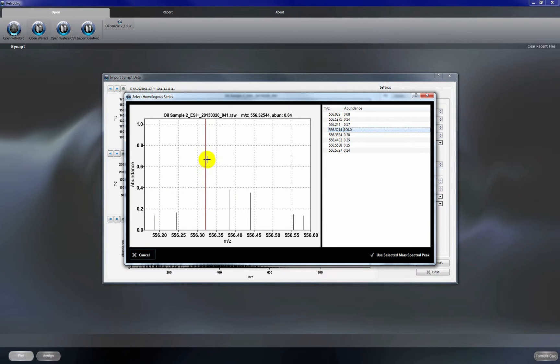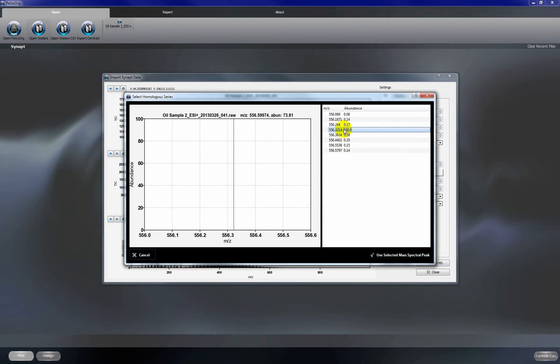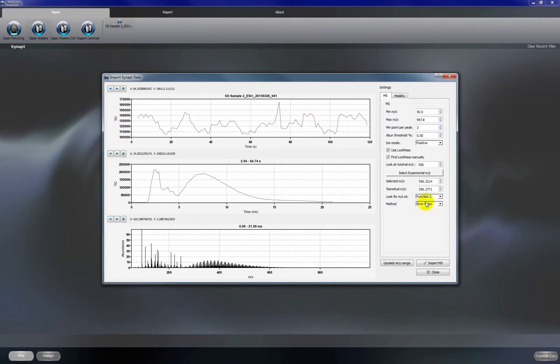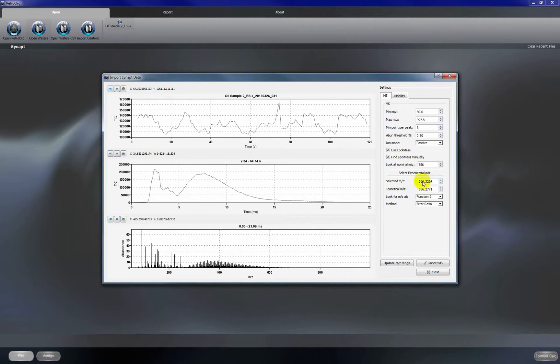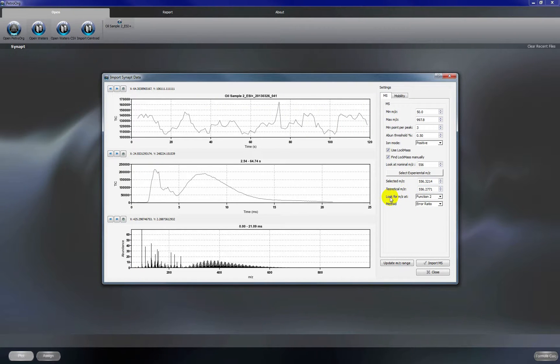When you click on these peaks they will highlight in red whichever one you've clicked and this is our actual lock mass peak. You can see here it's highlighted in red. When we zoom out by right clicking you can see that that's the most abundant peak. Once we highlight this, we'll select use selected mass spectral peak. So that plugs in the measured M over Z to this selected M over Z box and then we have our theoretical M over Z here so this is what we're going to use for our initial calibration.